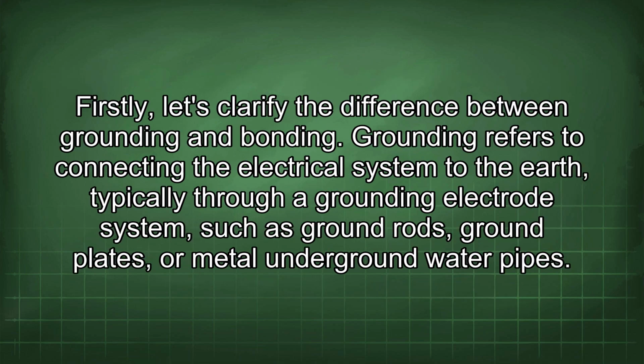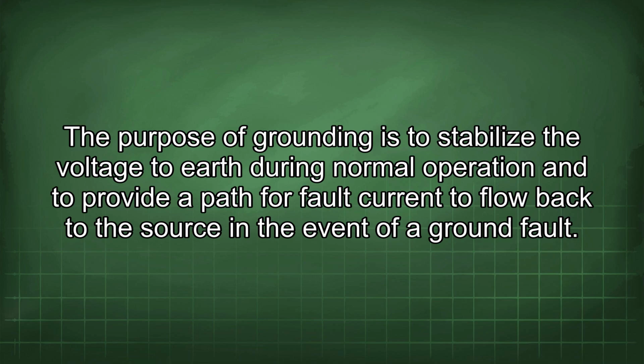Firstly, let's clarify the difference between grounding and bonding. Grounding refers to connecting the electrical system to the earth, typically through a grounding electrode system, such as ground rods, ground plates, or metal underground water pipes. The purpose of grounding is to stabilize the voltage to earth during normal operation and to provide a path for fault current to flow back to the source in the event of a ground fault.